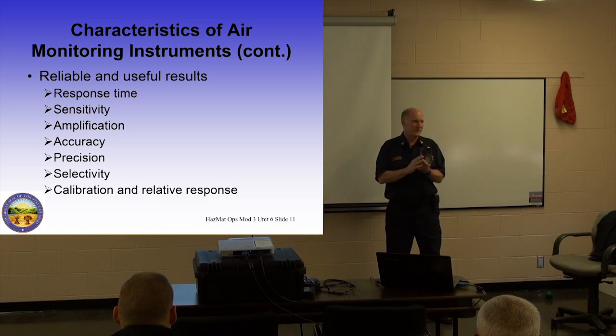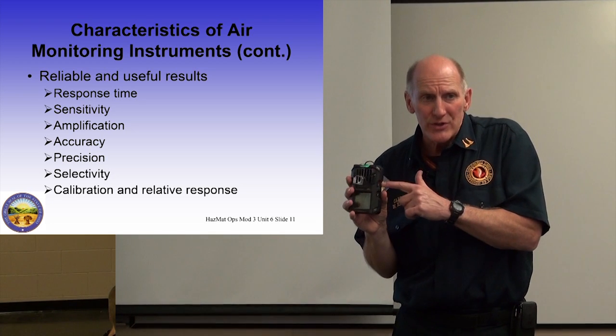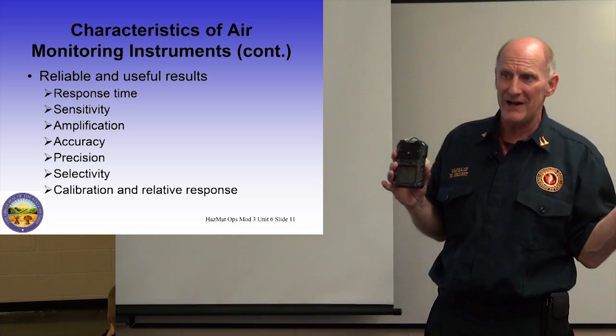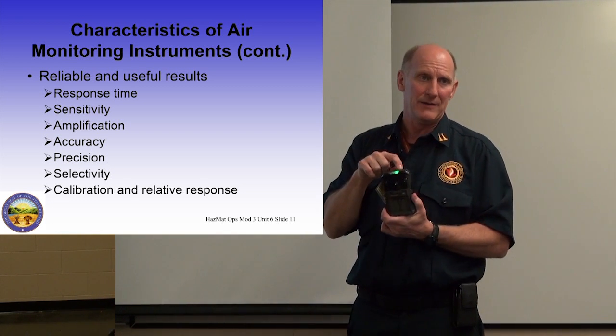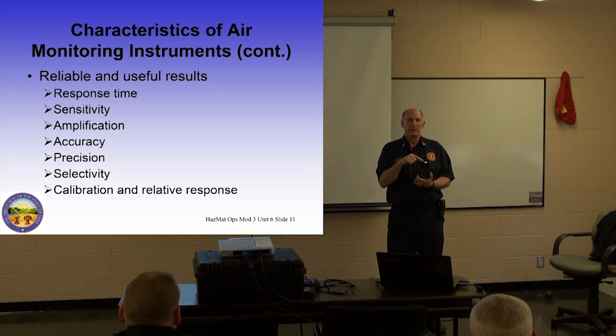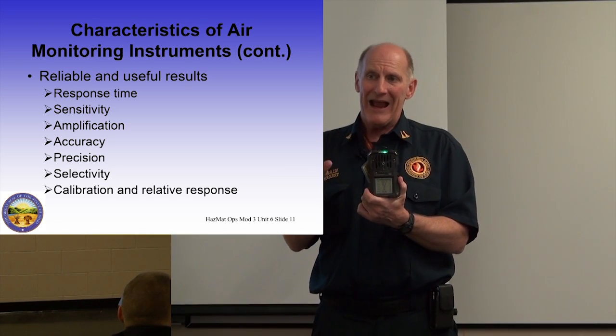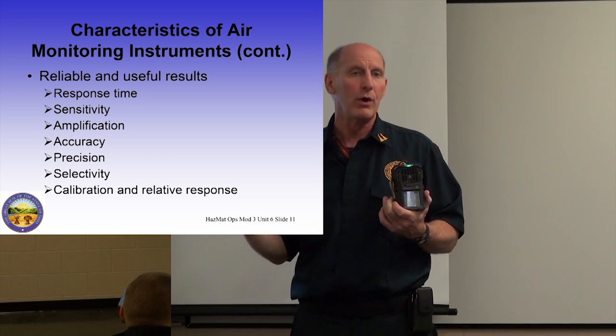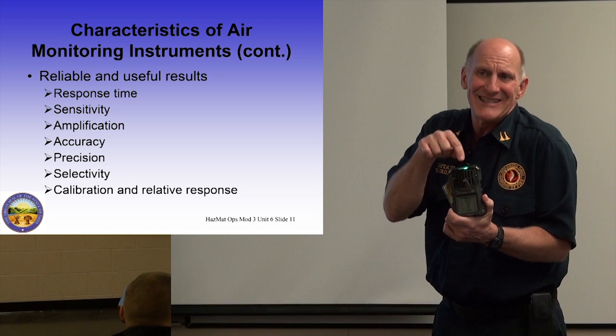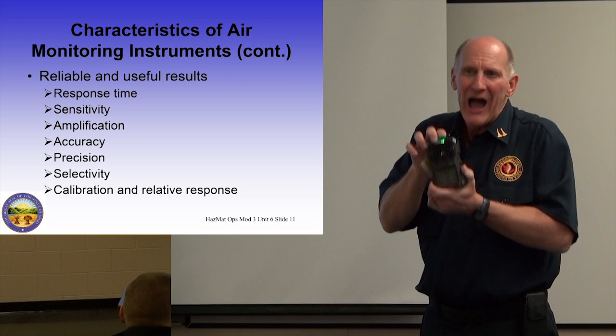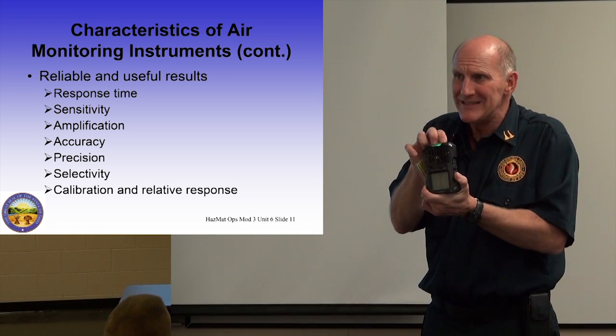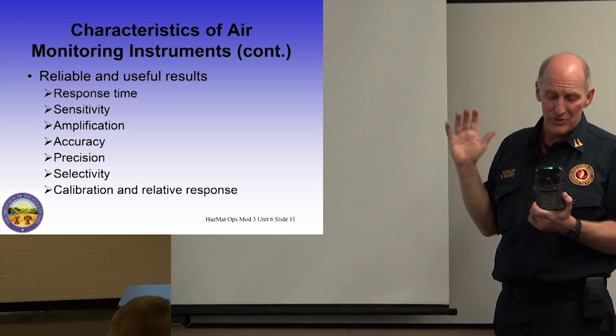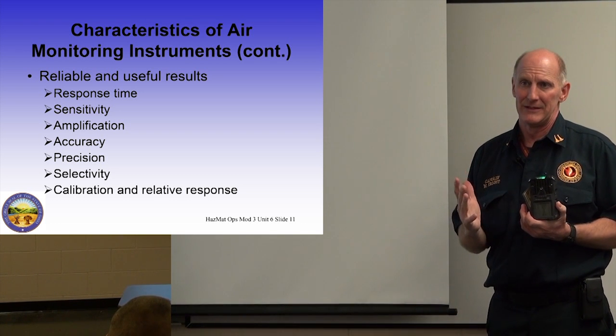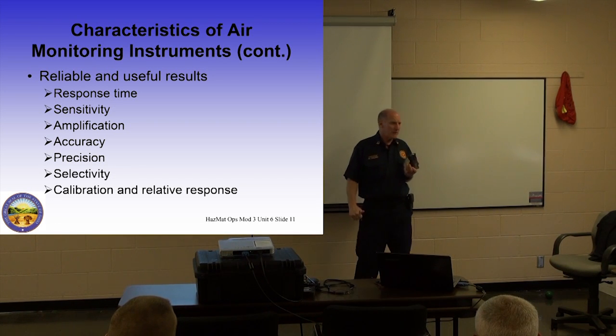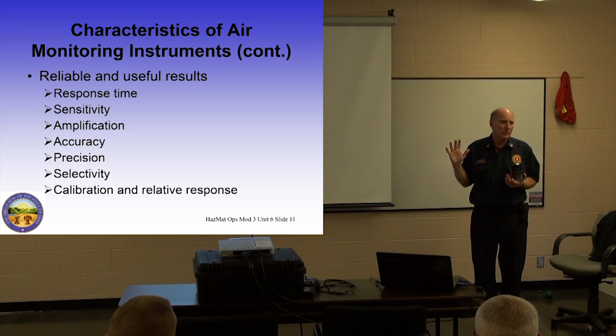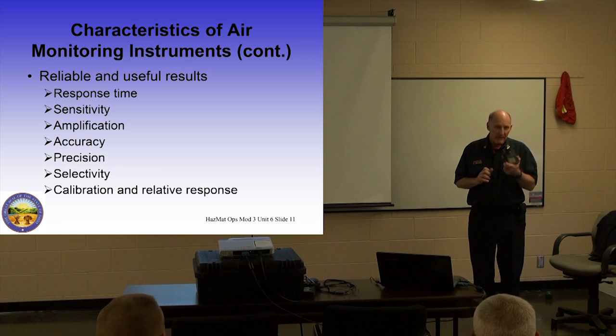That's the calibration. Relative response. If I am an industrial hygienist and I use this instrument in my business to make safe entries into a confined space, I better understand that when I calibrate this to methane, but I'm smelling propane, it's not accurate. And so I have to go into the books and I have to get the response curve and I have to take the actual reading and then I got to times it by a special number for propane because it's calibrated to methane in order to come up with the exact readings. We're emergency responders. I don't care how exact the reading is. The exact reading means nothing to me. And what we're going to use this instrument for is an indication that something is present. If, again, you dive into the relative response curves and you understand them, fine, but you'll eventually come to the conclusion that I don't need to know it as an emergency responder. The information is there.